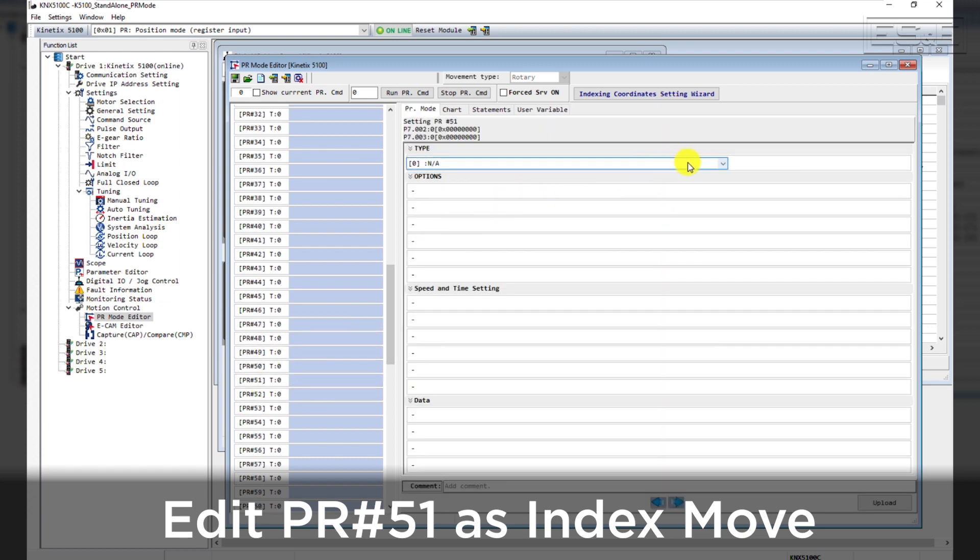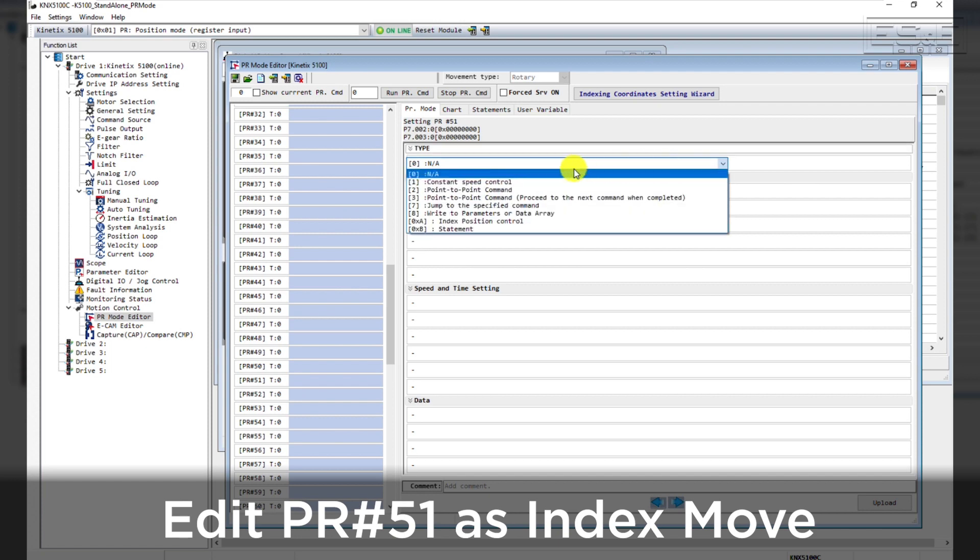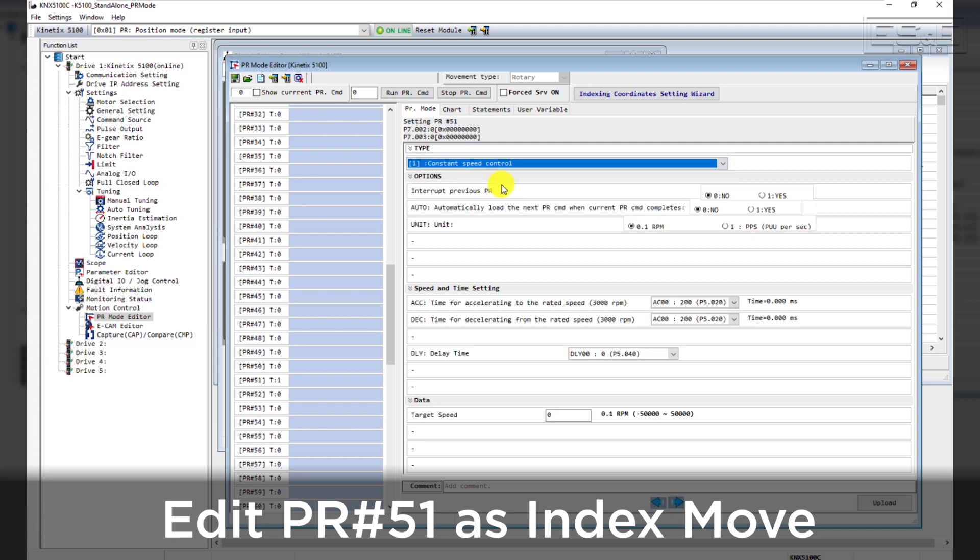This is where you can configure the index that will operate when DigitalInput 3 goes high. We will select Constant Speed Control for this example and then set the target speed to 200 RPM.